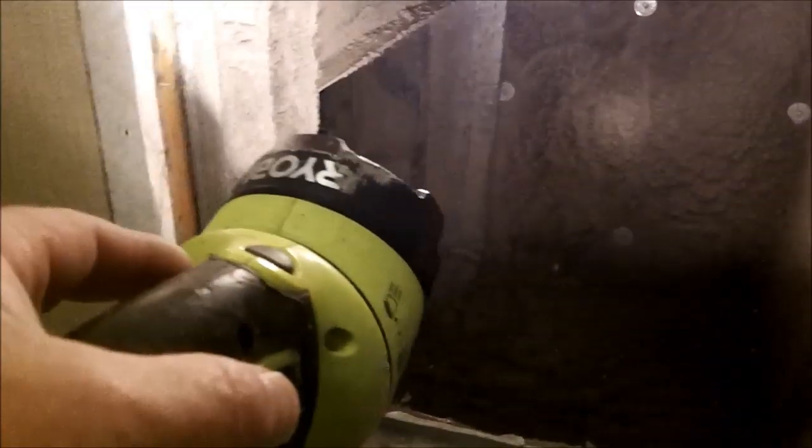Here is the return - that's a 14 by 14 hole, and there is an 8-inch fresh air duct. If they wouldn't have put that in, it really would have been bad. But anyway, that's the only return for that three-ton unit. We'll go look at the other side.